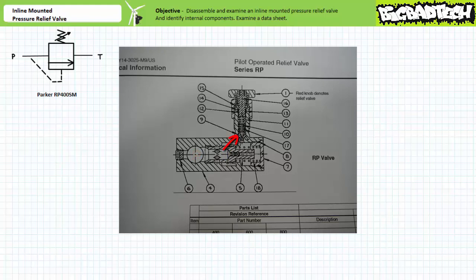A small passageway conducts fluid to the pilot chamber. You can see the dart, seat, spring, and manual adjustment knob. When pressure in the pilot chamber unseats the dart, the balanced piston unbalances, slides right, and opens the passage from P to T. When the dart in the pilot chamber reseats, pressure equalizes and the light biasing spring closes the passage from P to T.